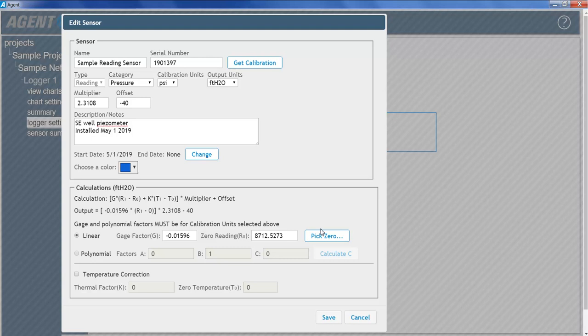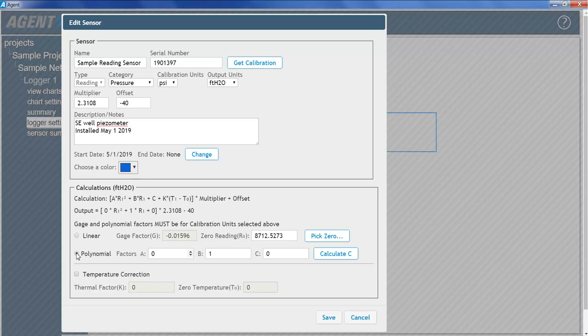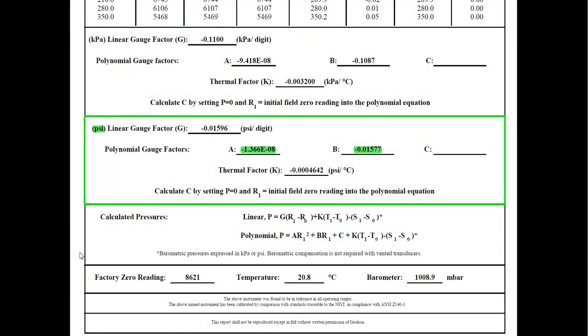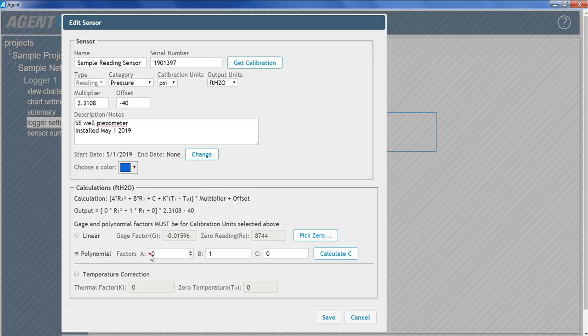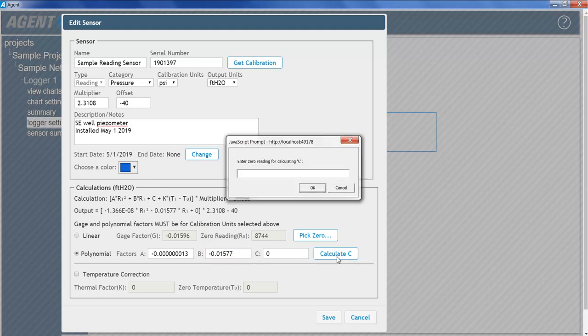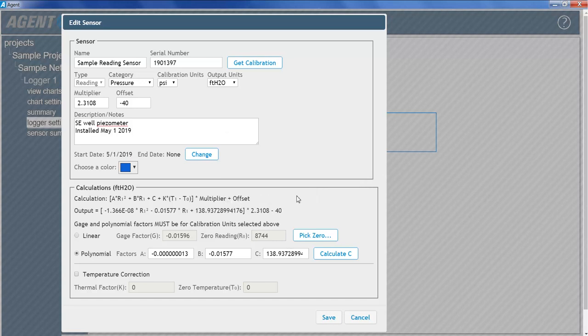For greater accuracy, the polynomial equation can be used in place of the linear equation. Enter polynomial factors A and B from the calibration report, making sure to use the factors that match the selected calibration units. Next, click on Calculate C. Enter the initial on-site zero reading. Then click OK. Agent will calculate and display the value of factor C based on the information entered.